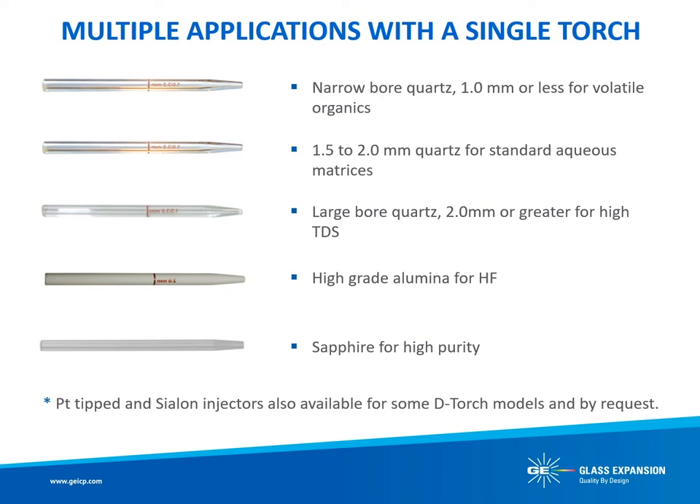The D-Torch can provide a laboratory analyzing several different sample matrices with significant savings in ICP torches. The D-Torch makes it easy to swap injectors of various internal diameters and material, providing the laboratory with a single torch that can easily be optimized for multiple applications. For example, a narrow bore of 1 mm or less is particularly useful for the analysis of volatile organics. For standard aqueous matrices, use an injector ID of 1.5 to 2 mm. Large-bore injectors are used for greater resistance to high total dissolved solids to prevent injector blockages — typically 2 mm or greater for high TDS. High-grade alumina is used for resistance to hydrofluoric acid. Sapphire can be used for high purity applications. Platinum-tipped and Sialon injectors are also available for some D-Torch models and by request.